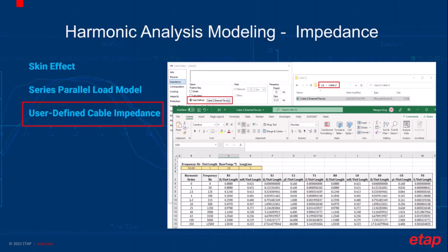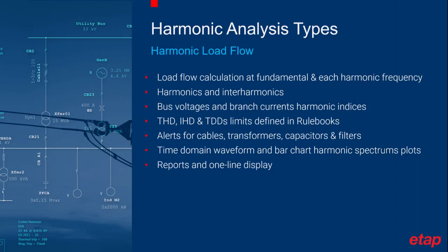Cable positive and zero sequence impedance and susceptance per harmonic order can now be user-defined in an Excel file and selected in the corresponding cable editors. I have included the directory to the Excel template in this slide. With the model set up, now you are ready to do the analysis.